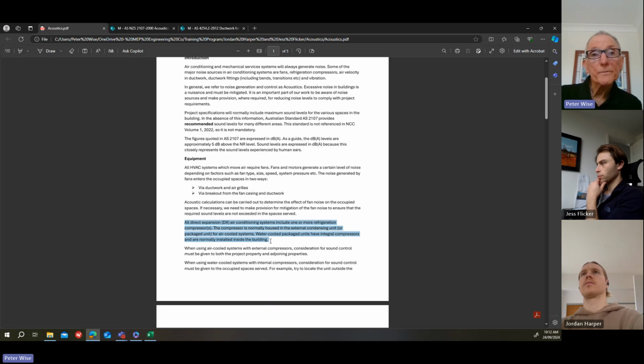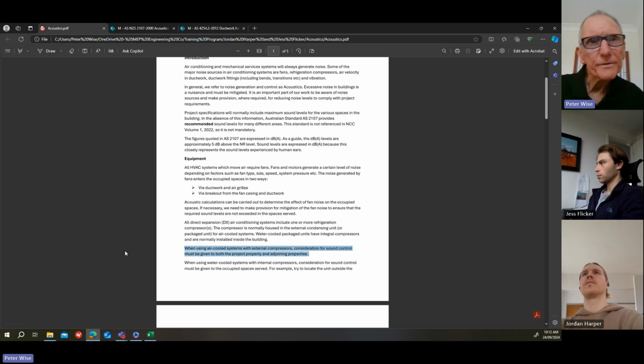So if you have a water-cooled package unit, they do make a bit of noise. I did a job in Sydney 5 years ago. It was actually a refurbishment. The original building had water-cooled package units in all the hotel suites, and it was noisy. It was very noisy, and they were trying to achieve 30 dBA in a bedroom, a hotel room. No way, you just can't do it. So we ripped all those out, and we put in a different system, which was just fan coil units connected to a chiller. But you'll come across those water cooled package units, and we may have a session where we talk about those sort of units.